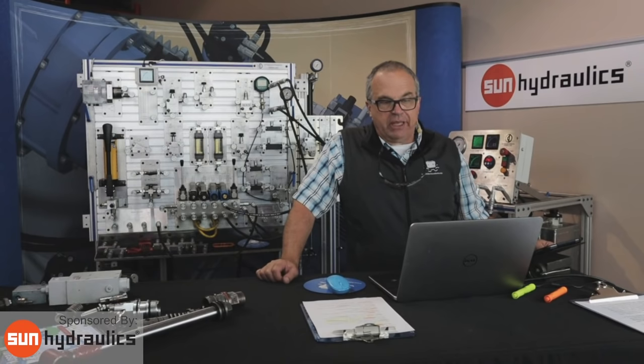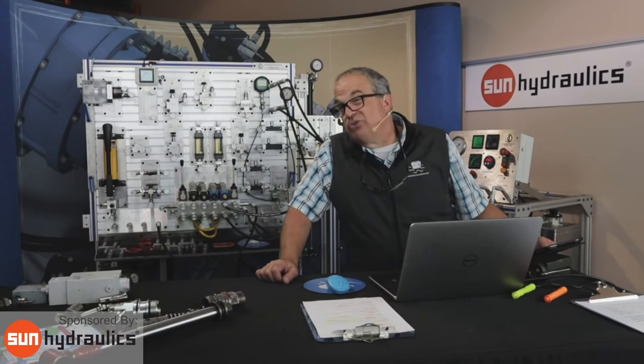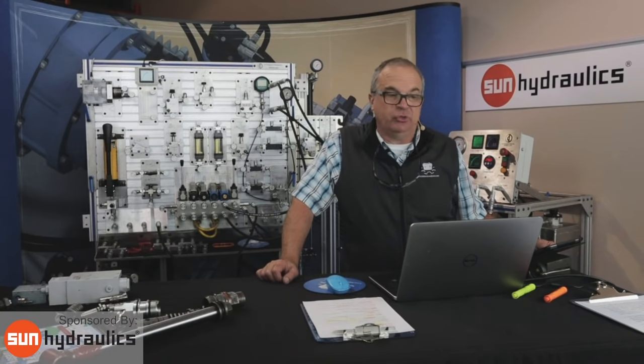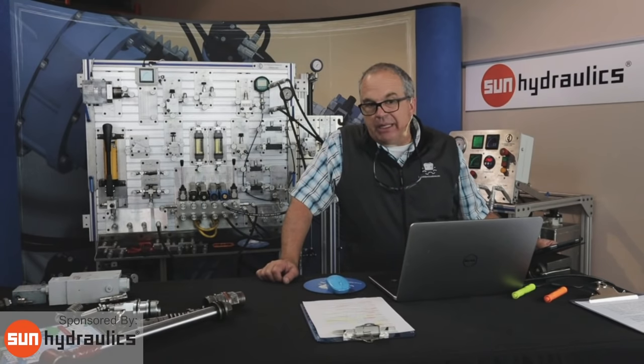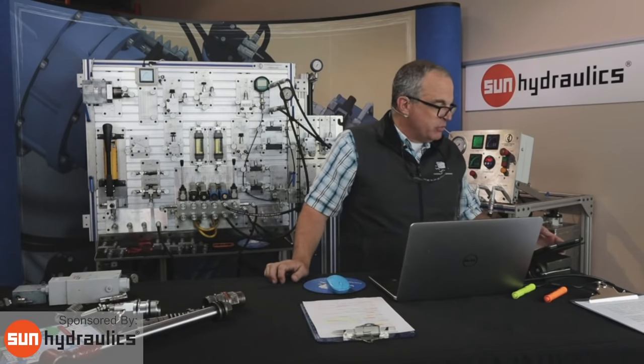hydraulic motors turning a generator set is probably what you're referring to, then quite often those are at the higher pilot ratios, like 10 to 1, because you're just looking for some soft braking and some generalized prevention of overrunning and not wanting to stop on a dime, which can be terribly hard on a rotating shaft.